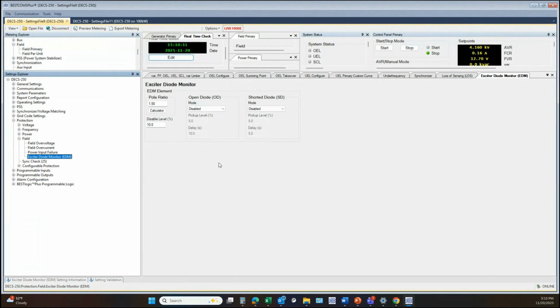The exciter diode monitor, I mentioned it earlier. You have to make sure you know the number of poles in the exciter and the number of poles for the generator, and so you have to develop this pole ratio so that you know the rate of the ripple current. So when the DECS is producing excitation, as that energy is being passed on through the exciter, there's a ripple current that rides on top of the excitation that the DECS is producing for these brushless excited generators. And the DECS can measure that ripple current. If that changes, it can detect it either as a shorted diode or an open diode in your brushless exciter and annunciate for that. So that can be set up if you have a brushless exciter and know those values for the number of poles.